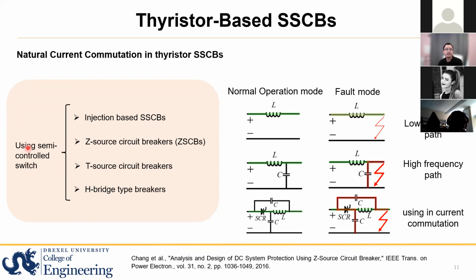Usually, for this semi-controlled device, the SSCB based on this could be classified into the injection-based SSCB, Z-source SSCB, T-source SSCB, H-source SSCB. So for different ones, they have a different circuit topology configuration. But the most popular one is the second one, the Z-source one. Here I want to explain the working principle. You could see in the normal operation mode, we have an inductor in the DC system.